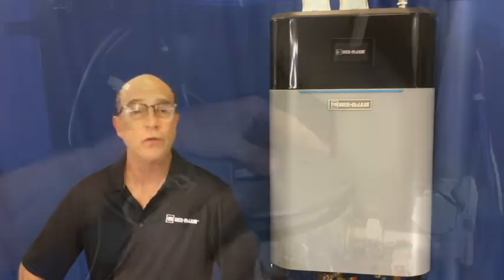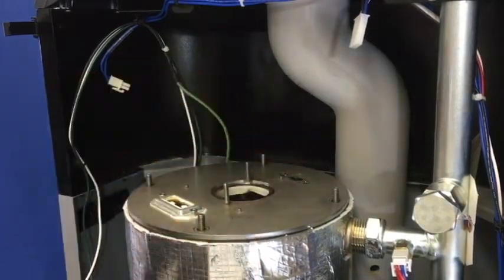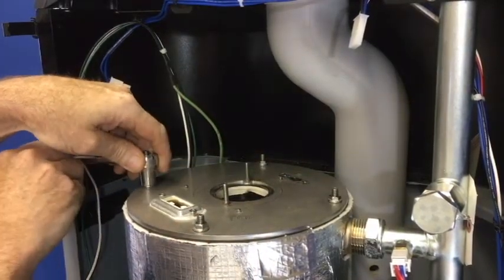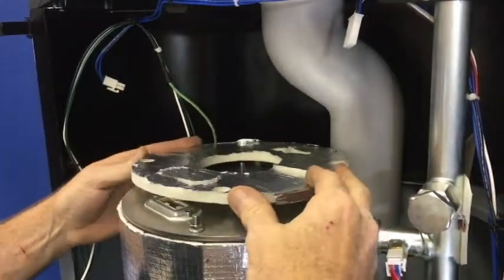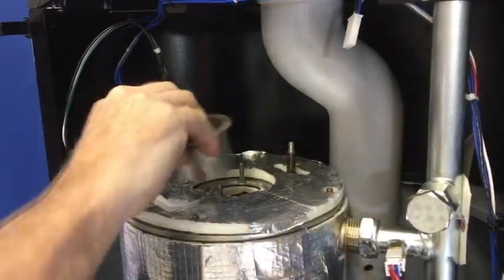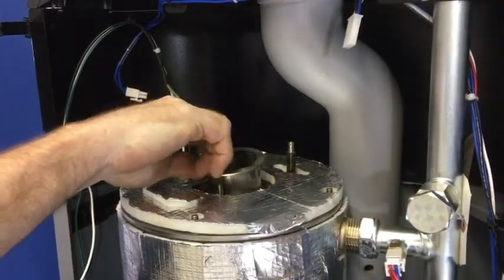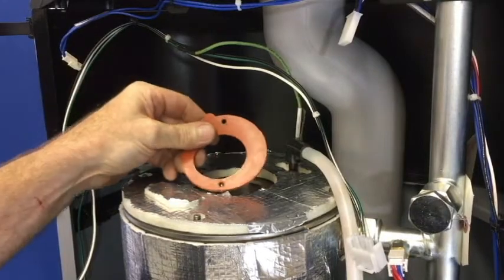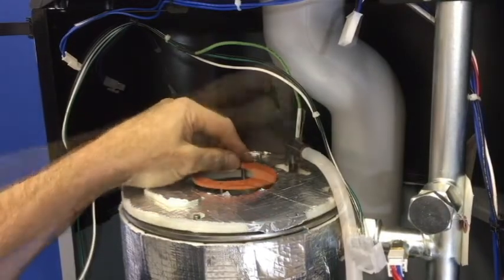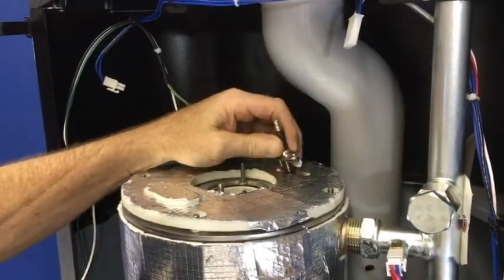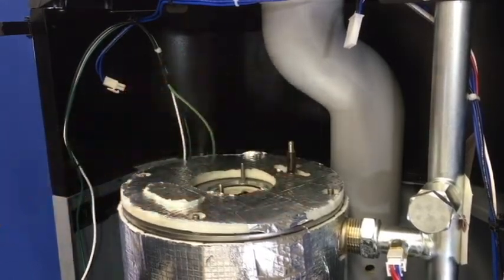Reinstall the control module, the burner, burner insulation and gasket onto the cover plate. Reinstall the igniter and gasket and the blower Venturi and gas valve.